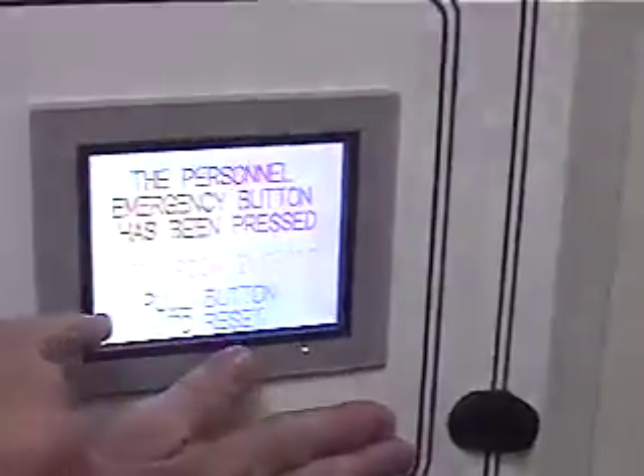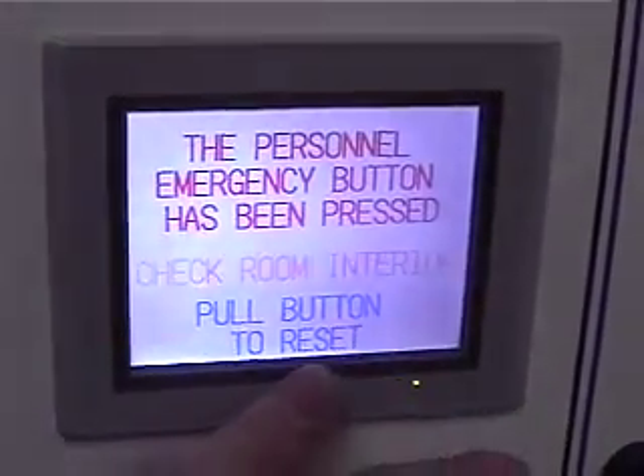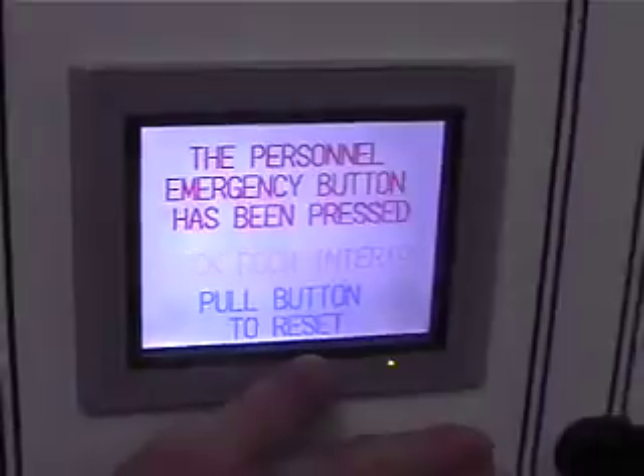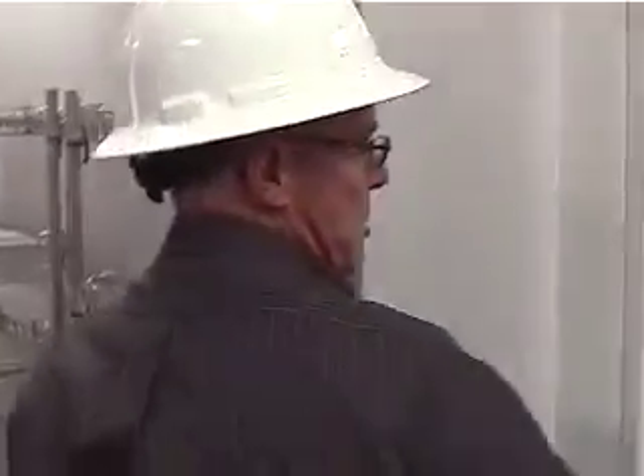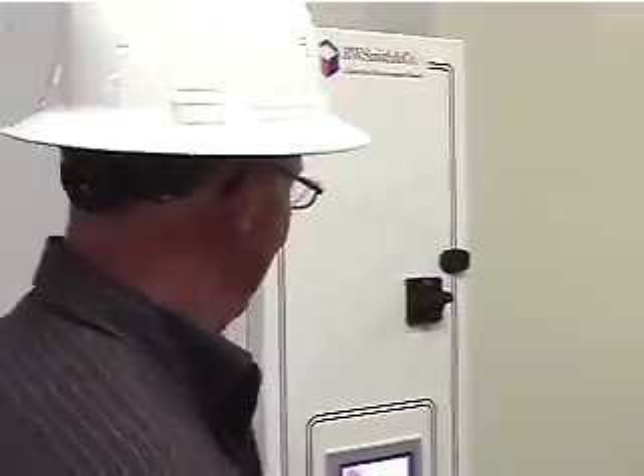We shut the refrigeration off, turn the lights on, energize this guy up here and this guy that you can hear, and have a little thing here that tells people you ought to check inside, move the body out of the way, and reset the button. You're a stiff punch. That always gets it. Reset resets everything.